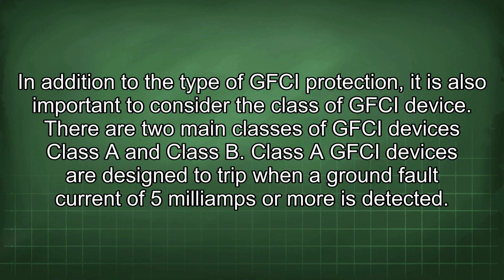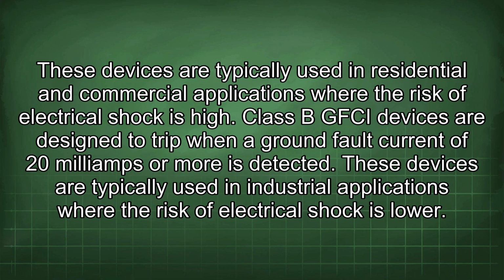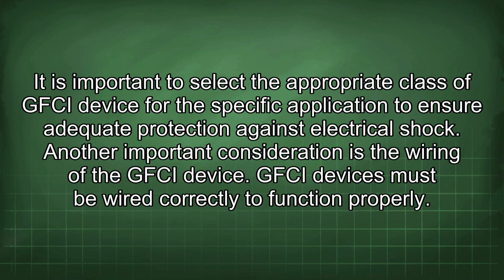of GFCI device. There are two main classes of GFCI devices, Class A and Class B. Class A GFCI devices are designed to trip when a ground fault current of 5 mA or more is detected. These devices are typically used in residential and commercial applications where the risk of electrical shock is high. Class B GFCI devices are designed to trip when a ground fault current of 20 mA or more is detected. These devices are typically used in industrial applications where the risk of electrical shock is lower. It is important to select the appropriate class of GFCI device for the specific application to ensure adequate protection against electrical shock. Another important consideration is the wiring of the GFCI device.